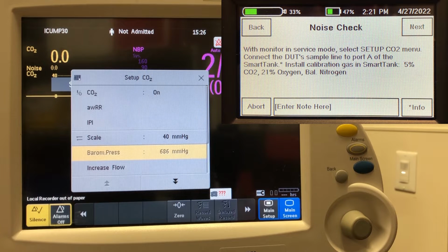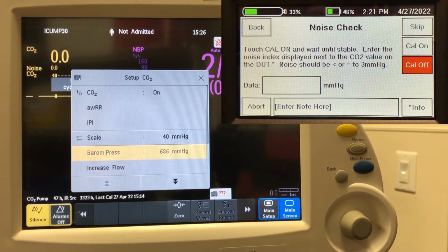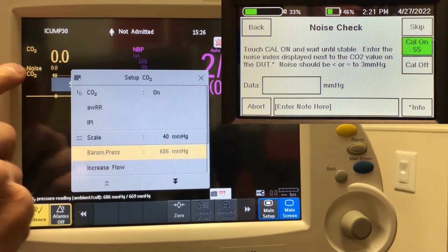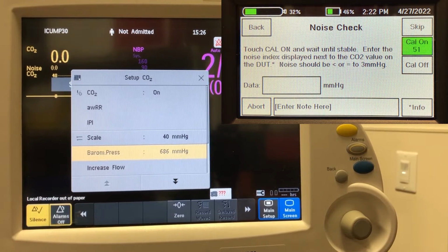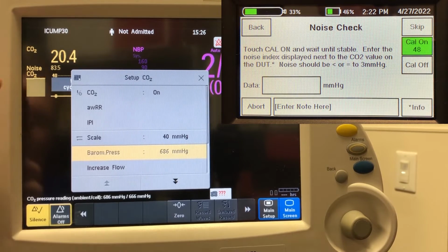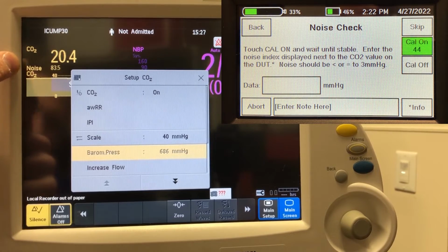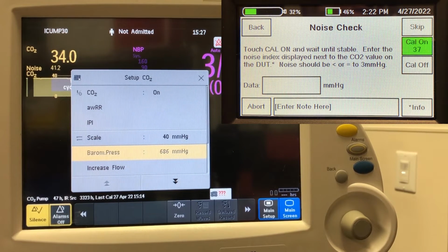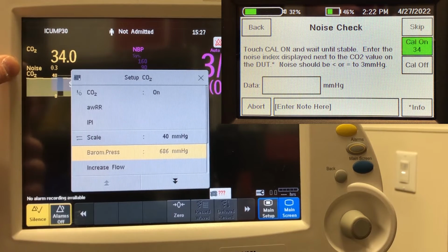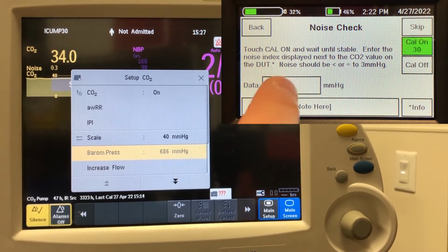So we connect the sample line up to port A on the Smart Tank. Make sure we have our 5% CO2 installed in the Smart Tank, and we navigate into the CO2 menu. So we're already in the CO2 menu. We're going to touch Cal on, and we're going to make sure that the noise reading, which is this little number right next to where it says noise, should read less than 3. We've got to give it a minute to level out because it was at no gas and it went up to gas, so it's showing a really big noise. So we got to wait until it's had enough time to stabilize. There it is. So see that noise level's dropped down to 0.3. So that's a pass.